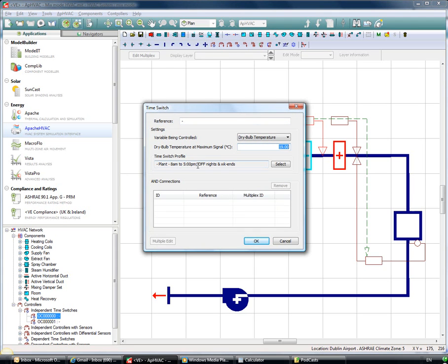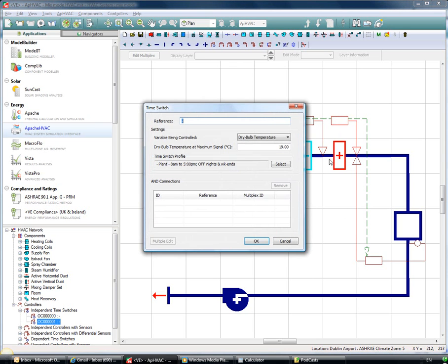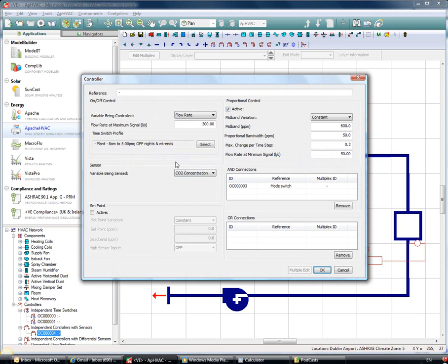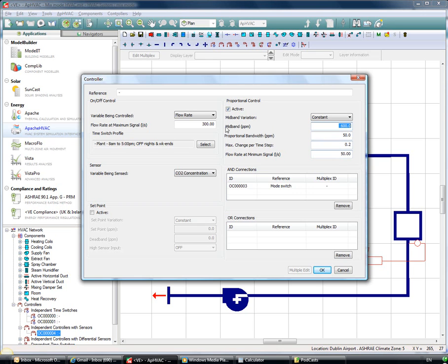We have this variable air flow varying between 300 and 50 liters per second. There again, similar to what we'd set up before, but this time we are controlling on CO2, so it's the ppm, the parts per million that we're controlling on, putting a mid band of 600 and a proportional bandwidth of 50, which means that once the ppm goes above 575 ppm, the air flow will start to rise until it's at its greatest flow rate when it gets to 625 ppm, and that's between the hours of 8 and 5.